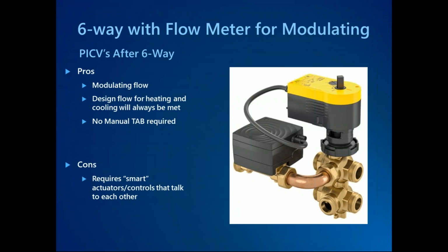You're still going to need your trim kit in terms of strainers and isolation valves, and somehow making up those 90s. But this can remove any additional balancing valves needed for the system. And all balancing would be done electronically through reading the GPMs in your flow sensor.